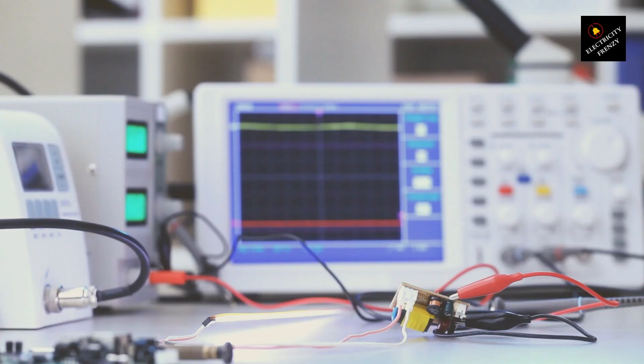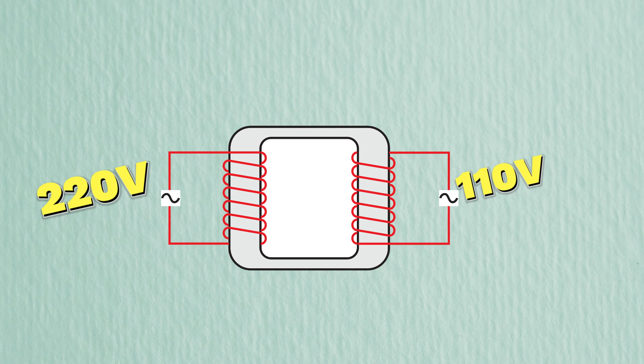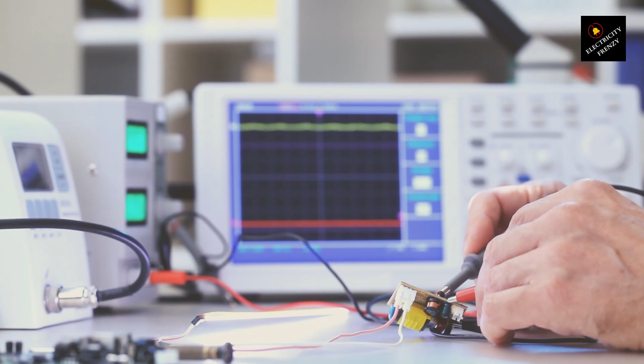Now, let's address frequency conversion. Unfortunately, converting between 50 Hz and 60 Hz is not as simple as using a transformer for voltage. To change the frequency, you'll need a frequency converter, which is a more complex and expensive device than a step-down transformer. Frequency converters take in electricity at one frequency, change it internally, and output it at the desired frequency. They're often used in industrial settings for machines that must operate at a specific frequency. But for most household appliances, unless it's a precision motor device or something frequency sensitive, a frequency converter may not be necessary if the voltage is properly adjusted.